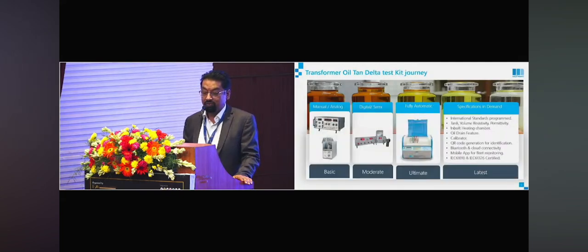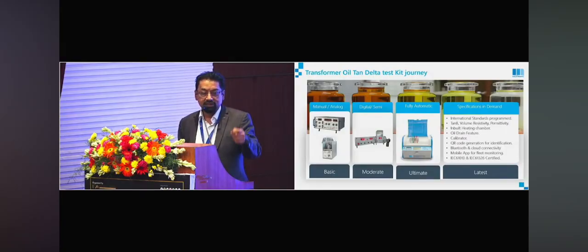The same thing is happening for the oil tan delta kit. The earlier kits had manual balancing with a separate heating chamber. Then the digital world came, and digital reading LED displays came. Now they want the heating chamber built into the equipment. So in this third equipment you can see an inbuilt heating chamber with the oil drain feature, with international standard programs, with Bluetooth and cloud connectivity. One more important thing: here also they are demanding the QR code so that oil samples can be identified. Here they are demanding a mobile app and Bluetooth connectivity. So this is what is changing with the technology, and the demands are enhancing.